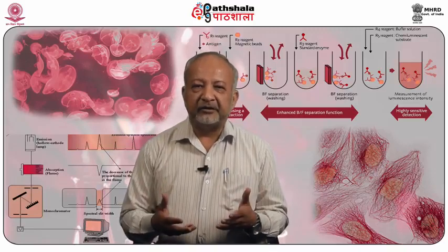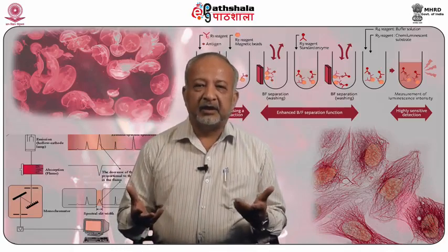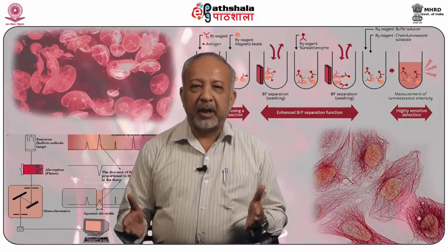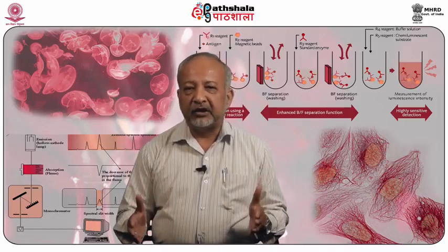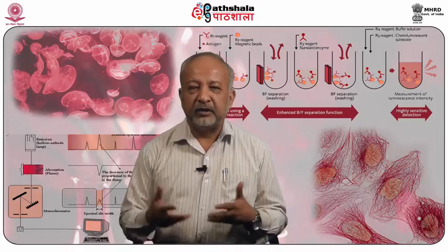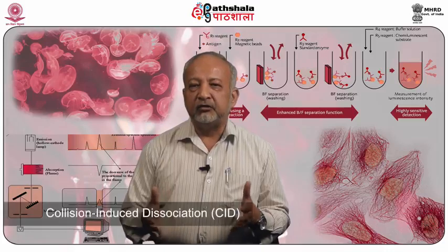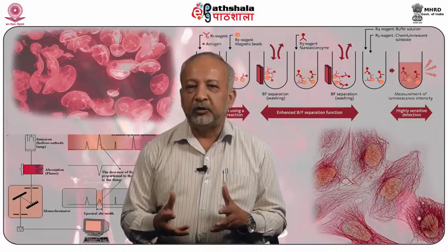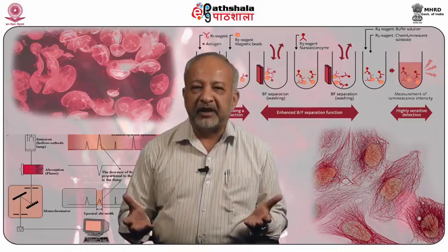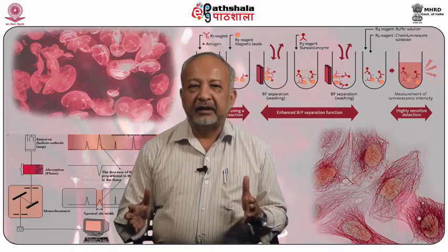They have a lot of benefits, such as they give classical mass spectra with unit mass resolution. They give good reproducibility. They are relatively small and low cost systems. That is why they are available in plenty in most of the laboratories today. Low energy collision induced dissociation, that is CID, MS spectra in triple quadrupole and hybrid mass spectrometers have efficient conversion of precursor to product ions.